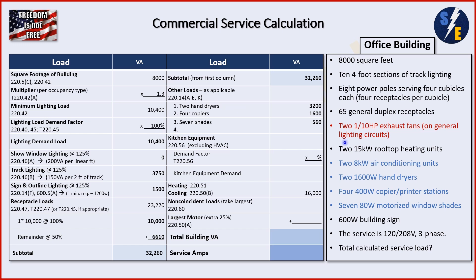We have two one-tenth horsepower exhaust fans, but they're on the general lighting circuits. Per 220.42, motor loads less than one-eighth horsepower on a lighting circuit are included in the general lighting load, so we don't add them here. The two 8 kW air conditioning units will go under cooling for comparison with heating later — two times 8 kW equals 16,000 VA. We also have two 1,600 watt hand dryers totaling 3,200 VA, four 400 watt copier/printer stations totaling 1,600 VA, and seven 80 watt motorized window shades totaling 560 VA. Kitchen equipment is non-existent.